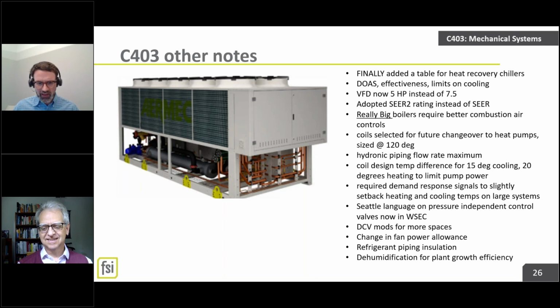So that's one of the magics of hydronics, that you get to keep the pipes and the pump. You might need to replace the coils in the building when you replace a boiler with a heat pump chiller, but again, we're getting better options so that maybe you don't. A lot of coils were already oversized. If it was sized at 180, but it was 50% too large, your 160 supply might get you there. Talk to your suppliers.